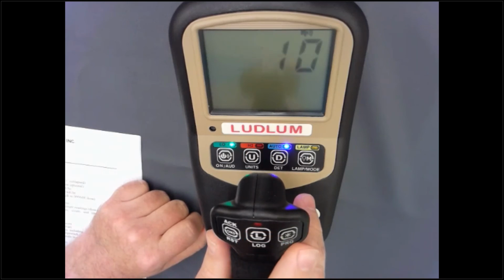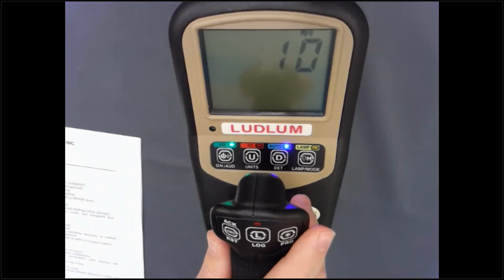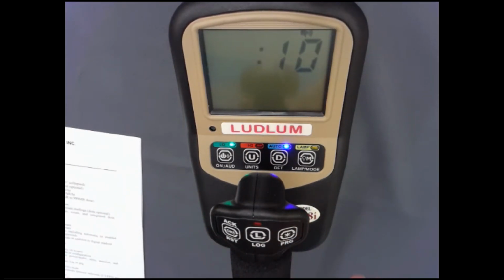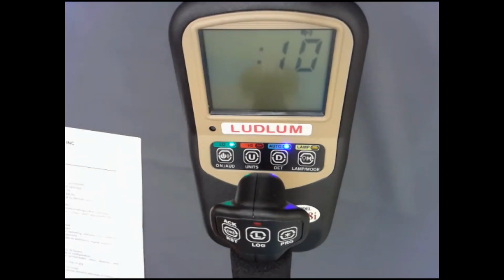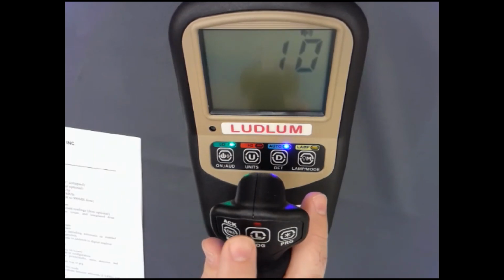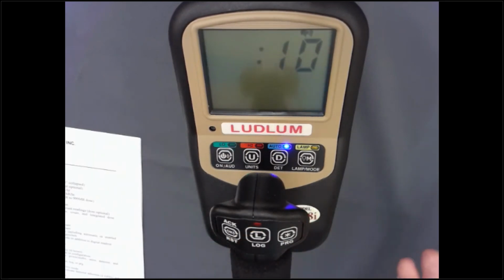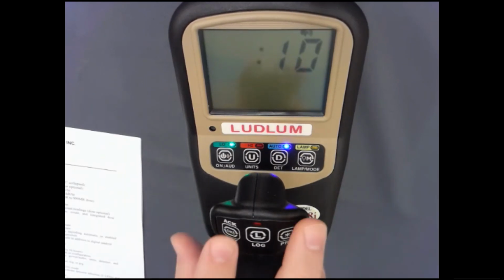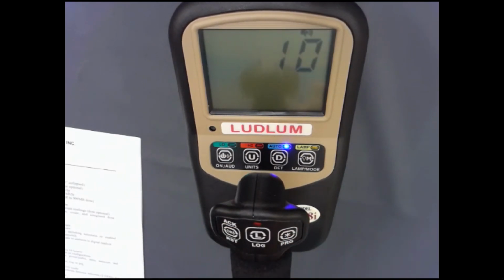Now, please note that we only have 3 digits on the display. So since we can't show a full 10-minute count, we shift 10 over and we start flashing the colon icon. When you see the colon flashing, that indicates that you're looking at minutes instead of minutes and seconds. And then you can initiate the count by pressing the log button, which will automatically just log it to your system, or you can press the ACK reset button 1 click, and it will just start counting down from there, and it will take all the readings for the next 10 minutes.